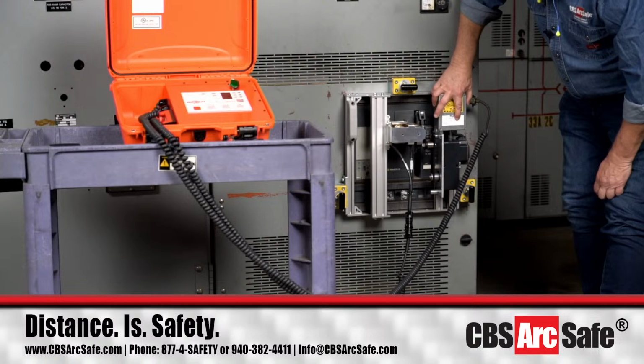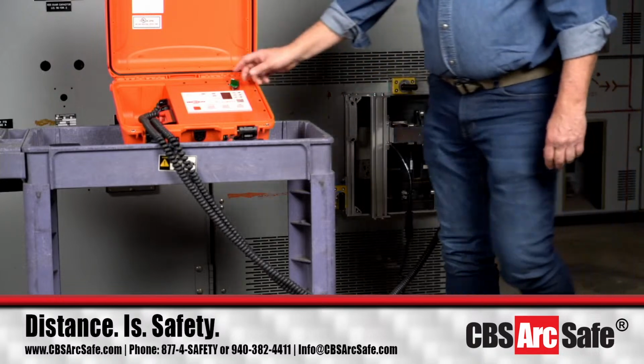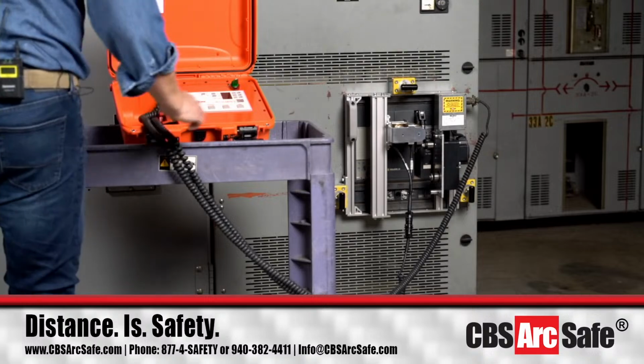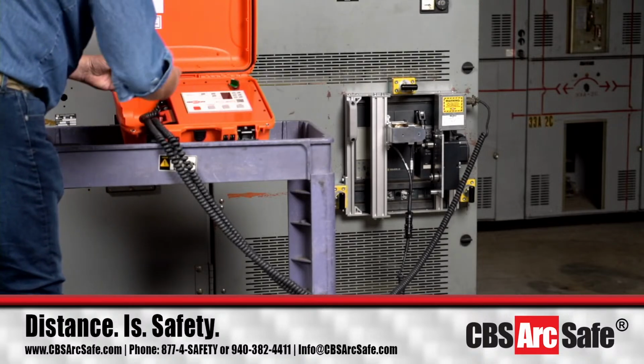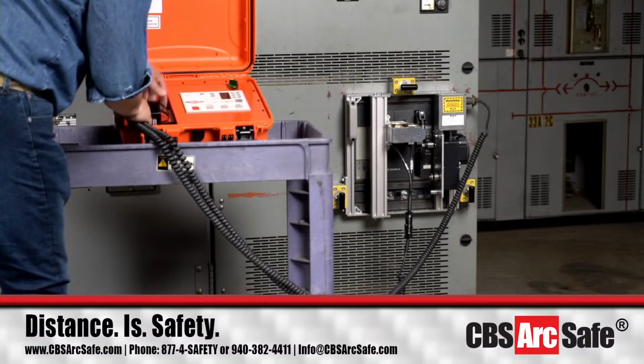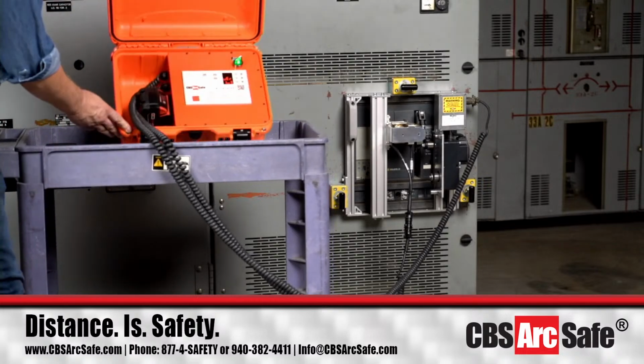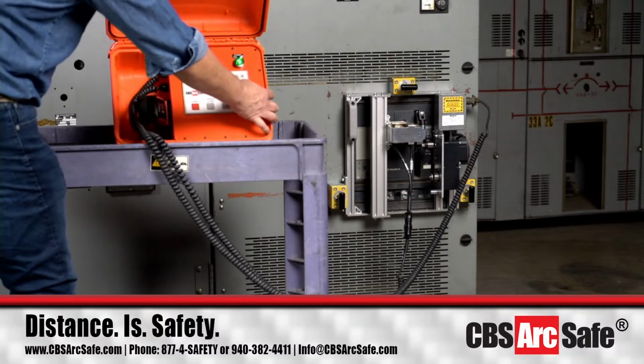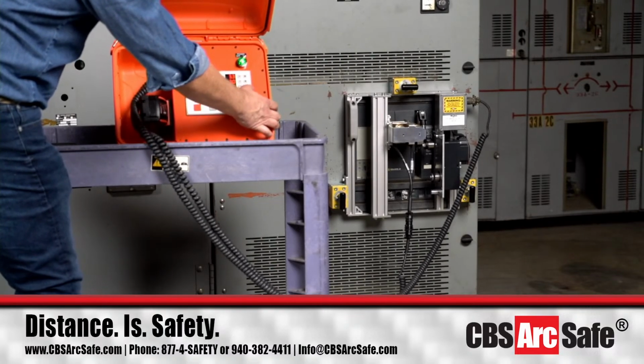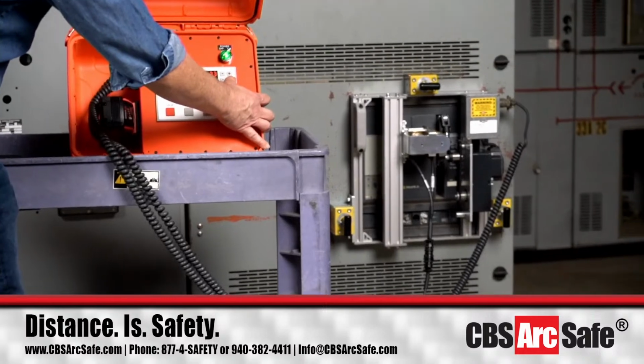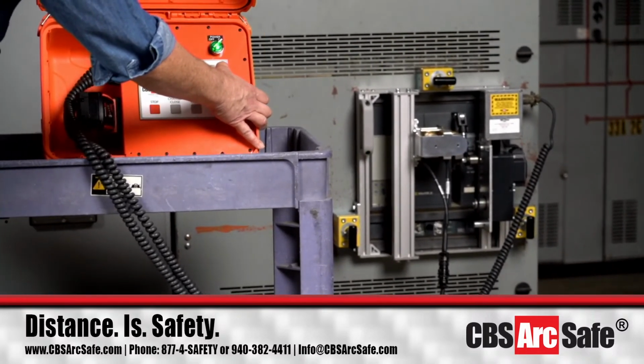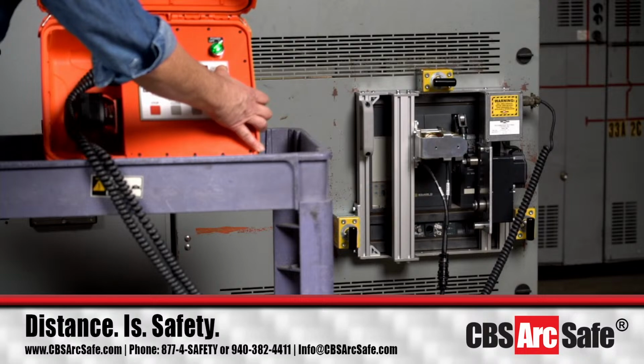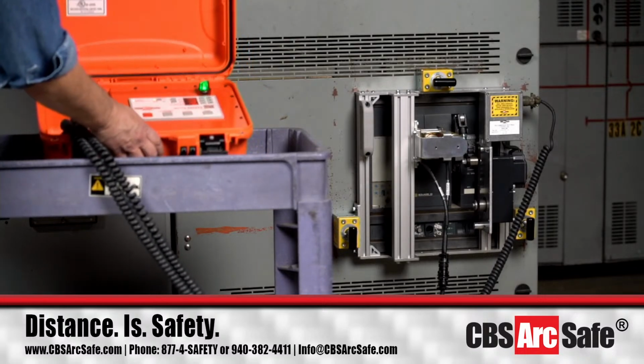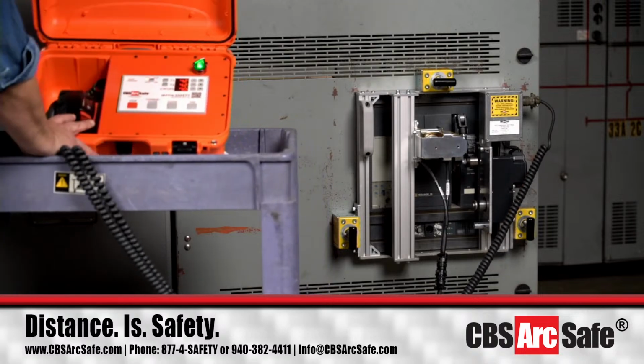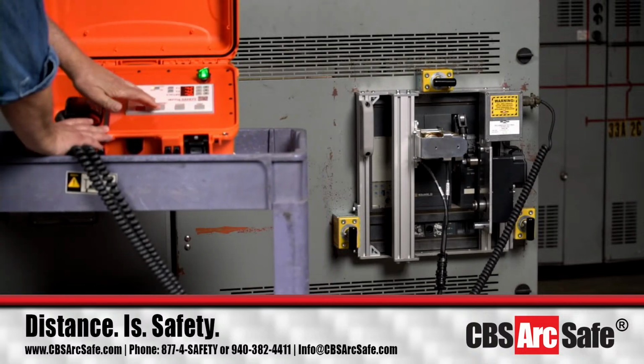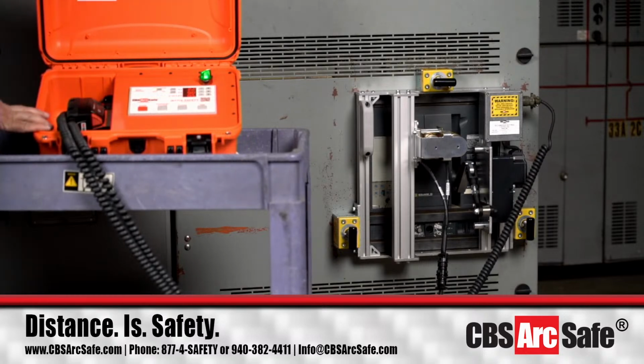Now this says 7, 4.2, and 4.2. So we're going to turn this—actually let me turn the power off. Let's get the breaker, let's get this back on here. Let's turn this on, and now I've got to make this read 7, so I'm going to go up 2, and then I'm going to go 4.2 and 4.2. And that's got that set now. So now, again, if I just hit charge close one time, we're going to start charging the breaker.